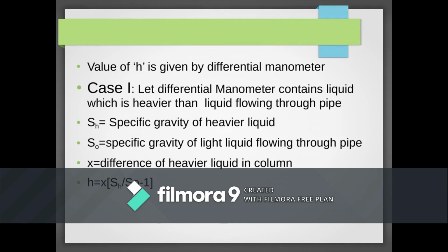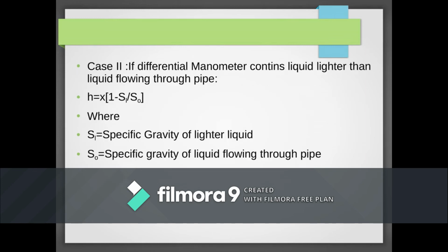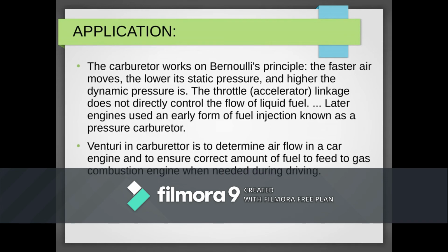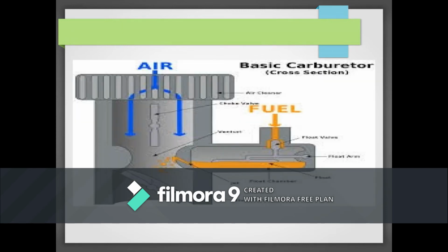Whereas at the inlet on the left hand side of the convergent part, the diameter is a little bit bigger, the cross section is bigger, the pressure is also high, and the velocity is low. So you can see there is a difference of pressure being induced. Now this difference of pressure can be measured by means of a differential pressure measuring instrument.